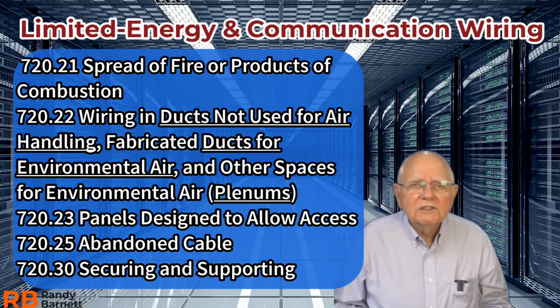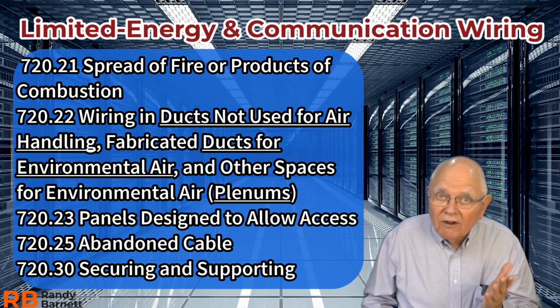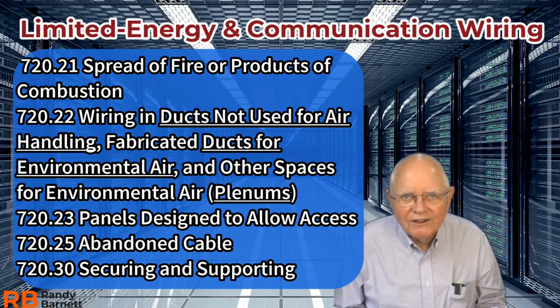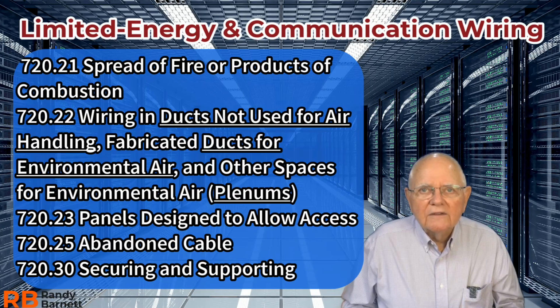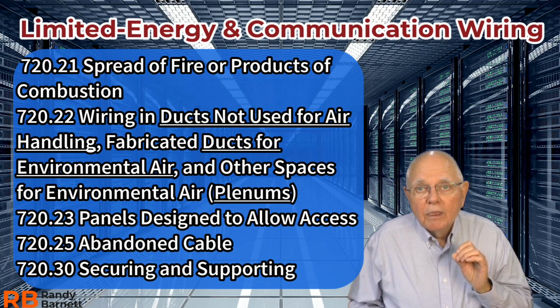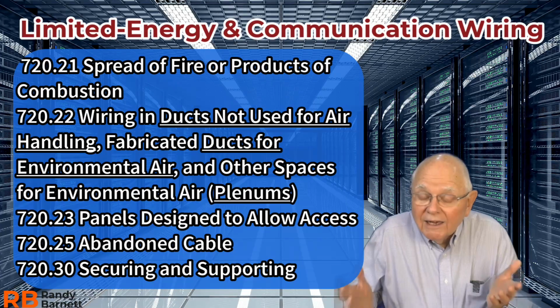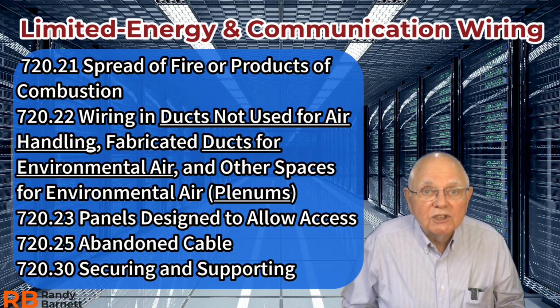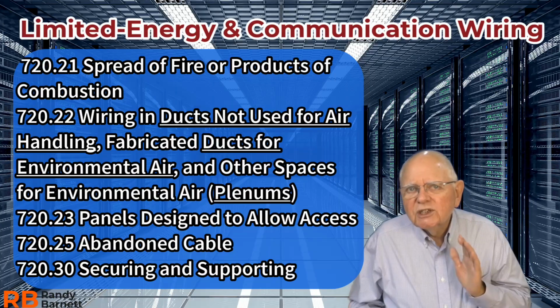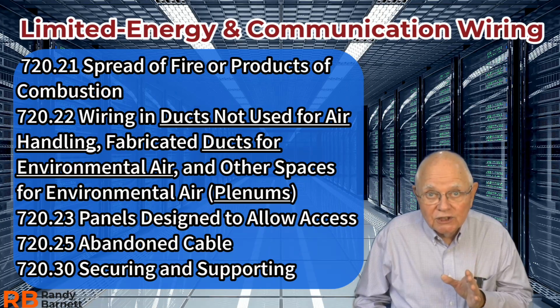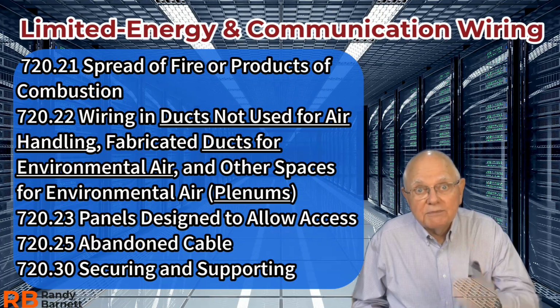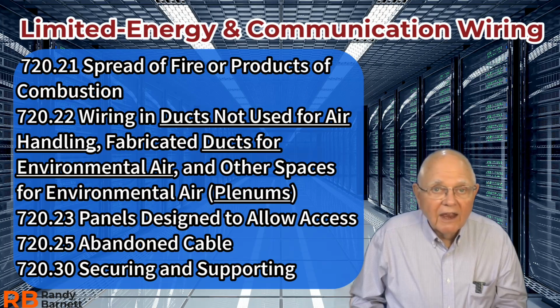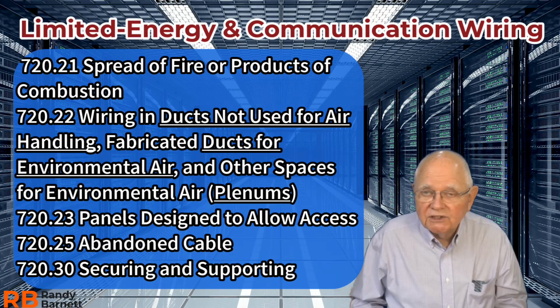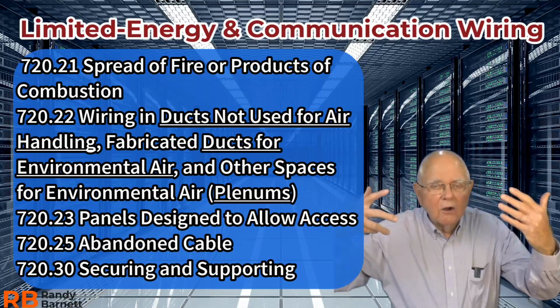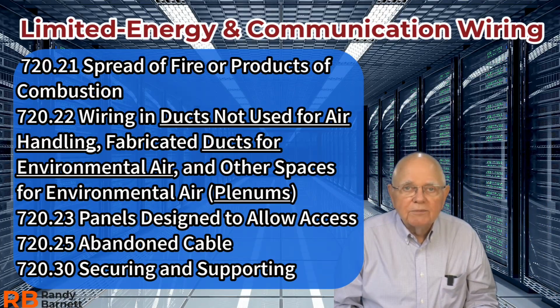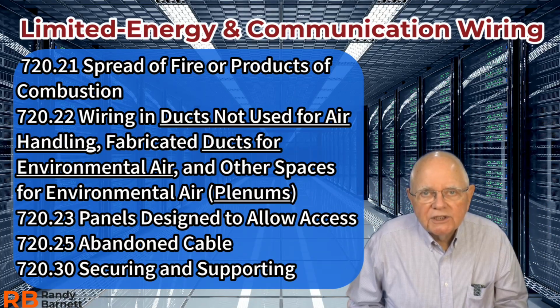Here are my securing and supporting requirements in .30, right? As we see elsewhere and throughout the code. Securing and supporting. The general rule is we've got to support our cables. Why do we do that? To prevent damage is what we want to do. Subsection B talks about limited energy cables above a suspended ceiling. It says I can't support those by the ceiling system. I can't use the grid wires that are holding the ceiling up to support my limited energy cables.